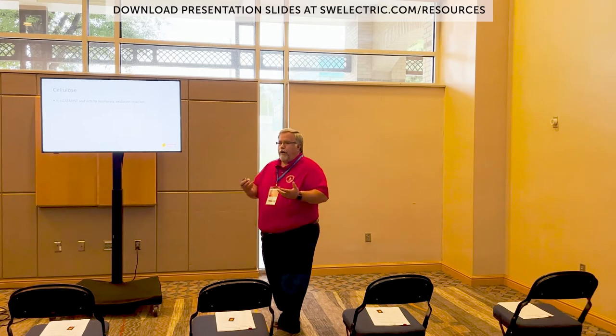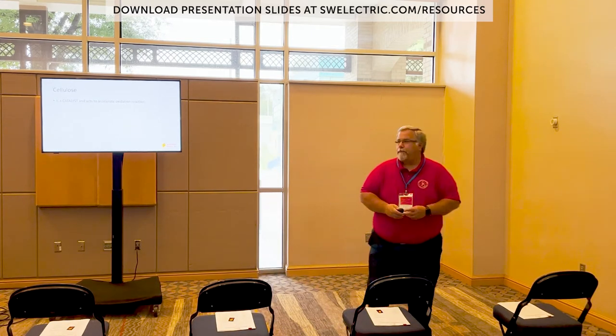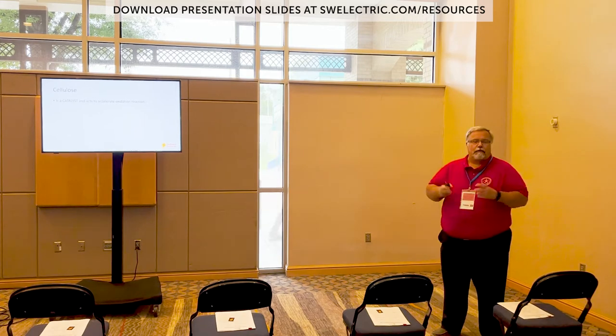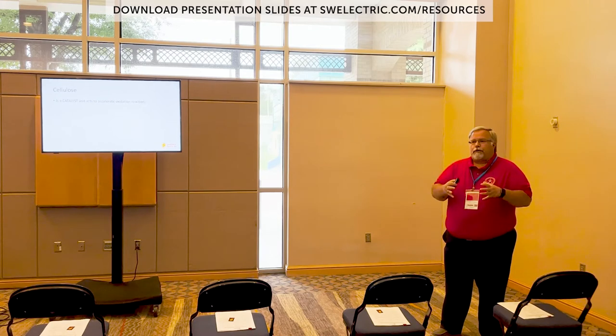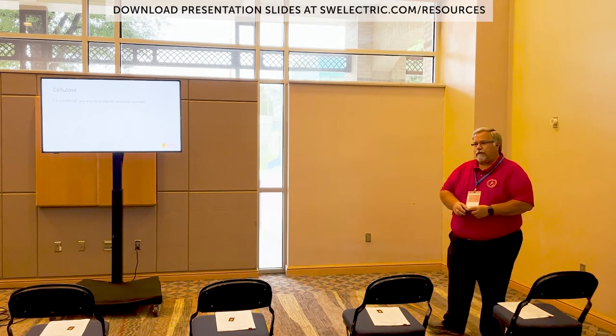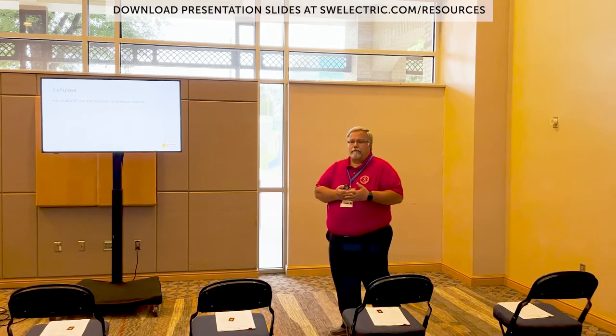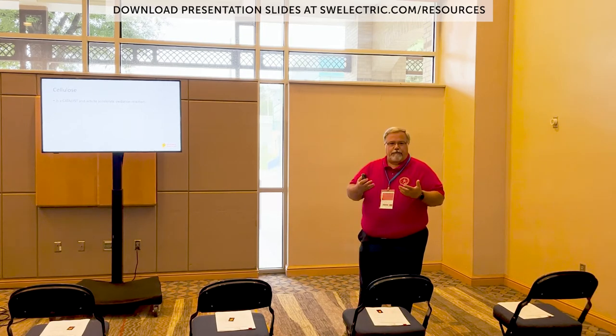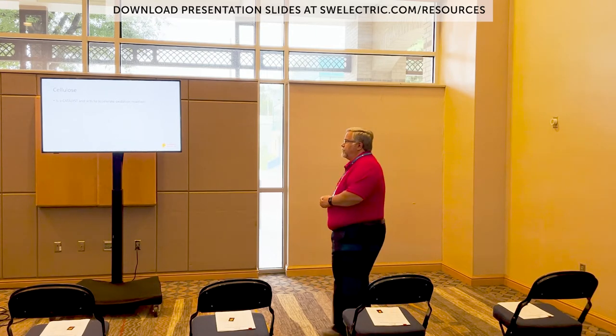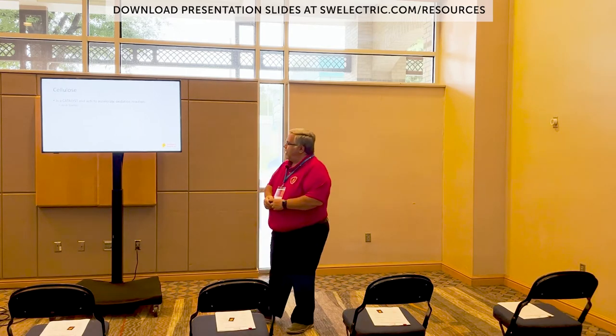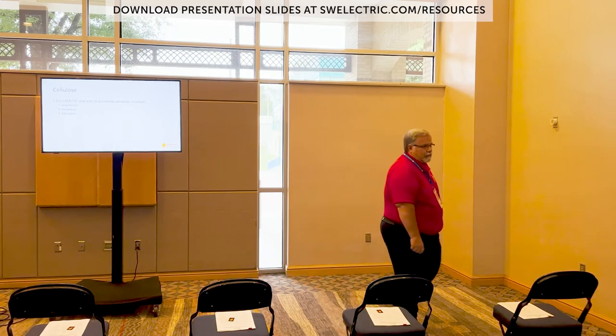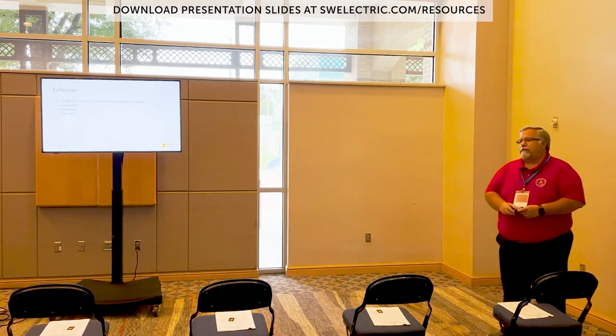Cellulose, it's a catalyst. So no matter what we do, transformers are going to age because of the paper. It's going to attract the polar compounds that are in the oil. Paper is a polar compound. Ketones, metallic soaps, things that are generated inside the transformer in the oil are also polar compounds, so they're attracted to each other. The paper is going to act like a big filter. As you've seen the inside of a transformer, you've got quite a bit of paper. That includes the cardboard, the wood, anything like that inside the transformer is considered paper. So it absorbs all that into it. But it's an acid former, it's an absorbent, and it's also an adsorbent. It's going to put things into the oil as well as take them out of the oil.